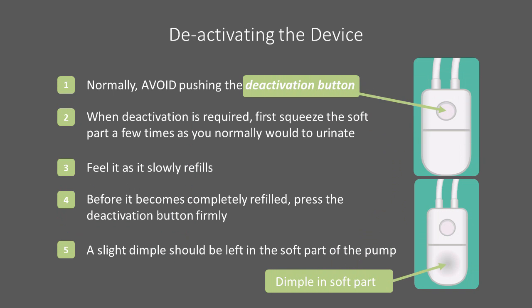Normally, one should avoid pushing the deactivation button. Deactivation is almost never required. In those rare cases when it is, however, follow these steps. First, squeeze the soft part a few times as you normally would to urinate, and feel the dimple of it as it slowly refills. Before it becomes completely refilled and the dimple is lost, press the deactivation button firmly. A very slight dimple should be left in the soft part of the pump.